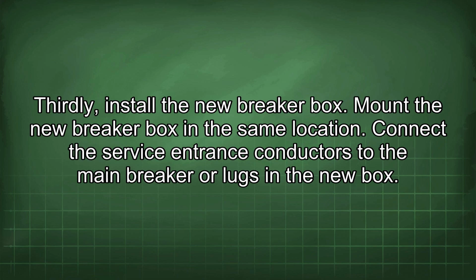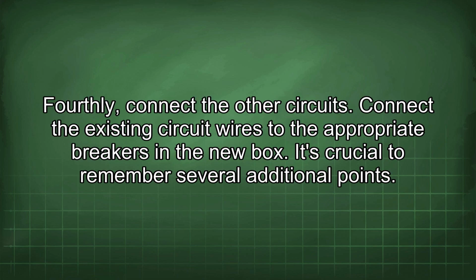Thirdly, install the new breaker box. Mount the new breaker box in the same location. Connect the service entrance conductors to the main breaker or lugs in the new box. Fourthly, connect the other circuits. Connect the existing circuit wires to the appropriate breakers in the new box.